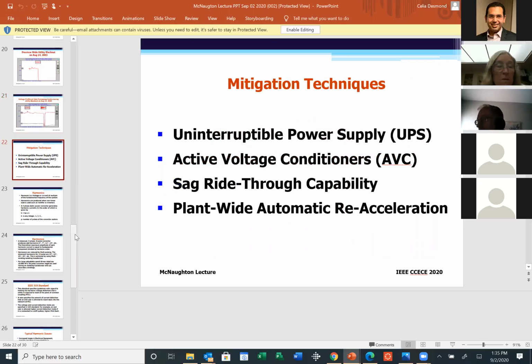Now, what do we do about this voltage sag issue? How do we go about protecting our plants? There are several ways that we can protect our commercial facilities, banks, data processing centers, but it really depends how much of that side we want to protect. The first one suggested here, which is commonly used, is the uninterruptible power supply, normally abbreviated as UPS. Normally, a UPS is used in most cases for a data processing center, because data processing centers mostly have computers, and those computers require less power. Typically, we're talking about anywhere from 30 to 50 kilowatts up to potentially 200, 300 kilowatts.